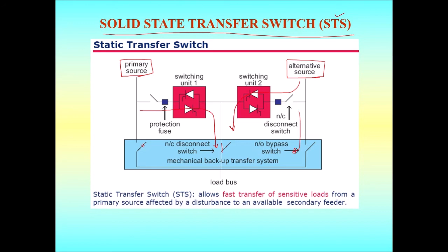When the fault takes place, this has to be switched off and this has to be switched on in a short period of time. Once this is off, current starts flowing through this for a short while, and finally it is slowly transferred to this switch, the continuous switch. So these units can be used to transfer the power very quickly from one source to the other without disturbing the load operation. Hence the solid state transfer switches allow the fast transfer of power.